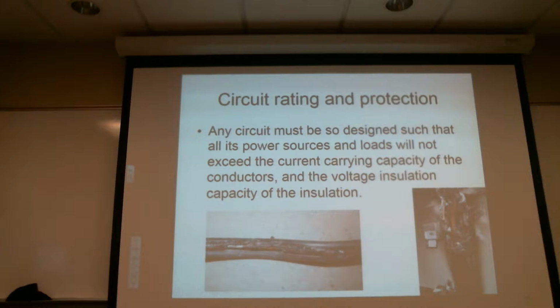because for the most part, most wire we make it to be good up to like 250 volts or something like that. Okay, and then even bigger wires, even better. But so when you look at the spec for mil spec wire, etc., the voltage rating on it's usually pretty darn high. So you can use it for 32, 24, 28, 120. It works for all of it. So we tend to disregard that value, but the truth is the rating for the wire needs to cover both insulation, so that the voltage doesn't leak out, and current carrying capacity, so that it doesn't overheat.